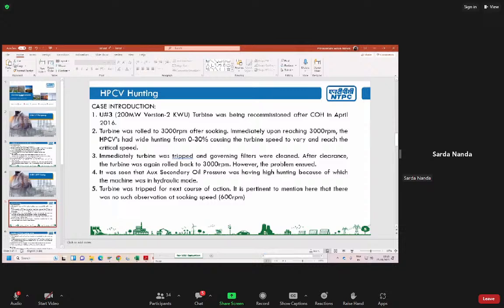After that, we saw that there was wide hunting in the auxiliary secondary oil pressure, which gave way to the fact that the machine was in hydraulic mode. And why should the auxiliary secondary oil pressure have hunting? That's the reason we tripped the machine. And then you see in the hydraulic speed governor, there are two auxiliary follow pistons. And these two auxiliary follow pistons should be perfectly balanced. Otherwise, there will be some variation in the auxiliary secondary oil.